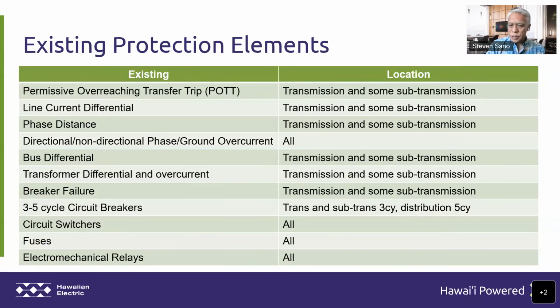For our transmission systems, our transmission lines, we have high-speed communication-based protection. Historically, it has been permissive overreaching transfer trip. For the longest time, this has served us well. We do have some limited line current differential protection, and that's becoming more important as we'll discuss a little later. Phase distance, also on transmission, has served us well. We have directional and non-directional phase and ground overcurrent everywhere in our system.